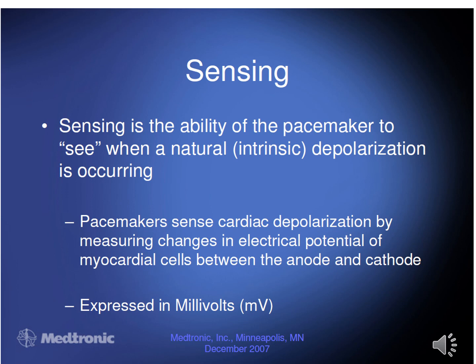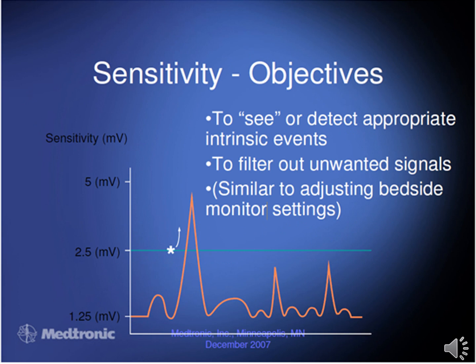Okay, let's talk about sensing. Sensing is when the pacemaker sees the patient's own rhythm. It's important because you don't want the pacemaker to fire in a vulnerable period and cause arrhythmias. Now this is expressed in millivolts. This next slide shows a good visual of the fence. When we talk about pacemakers, we use a fence analogy to help us figure out: is the pacemaker too sensitive? Is it sensitive enough?